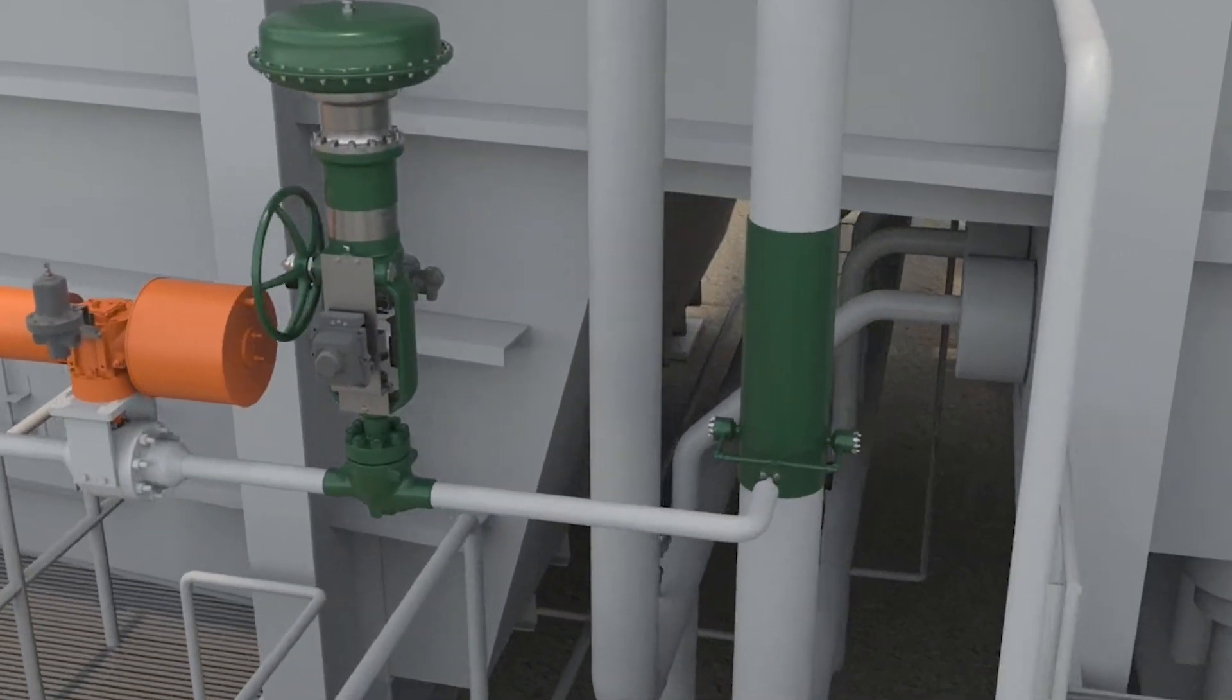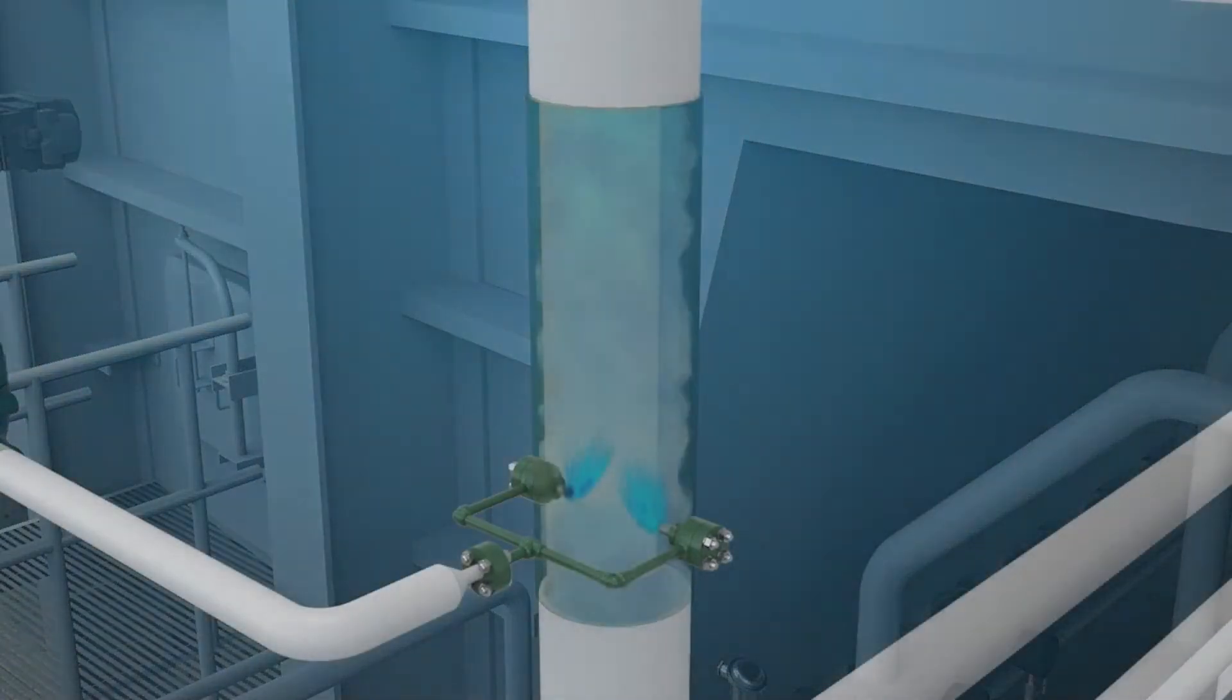The control system measures the temperature of the steam, compares it to set point, and then increases or decreases the spray water accordingly to maintain temperature set point.